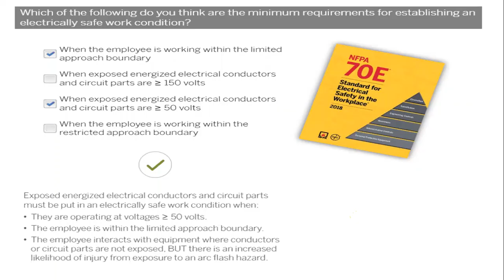Just like a candle, when you bring the candle close to your fingers, it does not necessarily have to touch your finger to cause a burn. When you come into some proximity, it causes a burn. Just like when dealing with electricity, when you come in very close proximity, even if you are not touching, there is a chance of electric shock by the jumping over of electrons. So for an electrically safe work condition, if you are working within the limited approach boundary and the voltage level is greater than 50 volts, you have to create an electrically safe work condition if you want to do work.